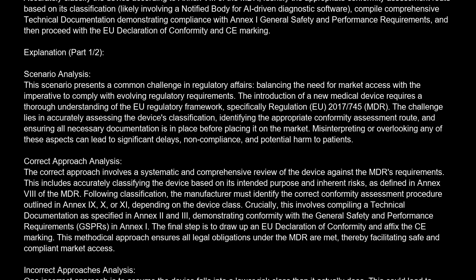of the MDR. Following classification, the manufacturer must identify the correct conformity assessment procedure outlined in Annex IX, X, or XI, depending on the device class. Crucially, this involves compiling technical documentation as specified in Annex II and III, demonstrating conformity with the General Safety and Performance Requirements, GSPR, in Annex I. The final step is to draw up an EU Declaration of Conformity and affix the CE marking. This methodical approach ensures all legal obligations under the MDR are met, thereby facilitating safe and compliant market access.